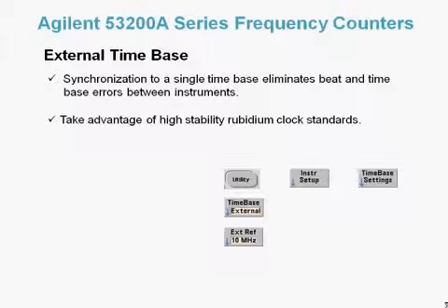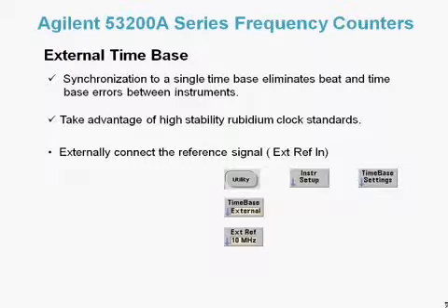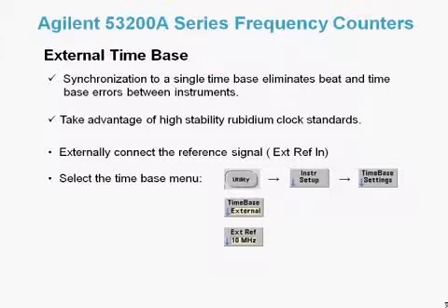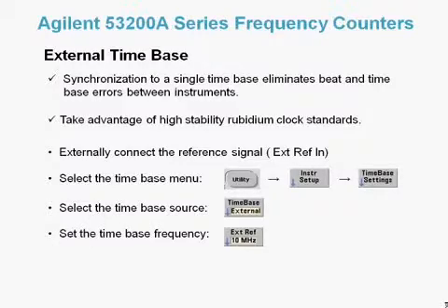Using an external time base with the counters involves externally connecting the reference signal — in this case it is connected to the external reference input terminal on the rear panel of the counter — selecting the time base menu, setting the time base source, and setting the time base frequency.